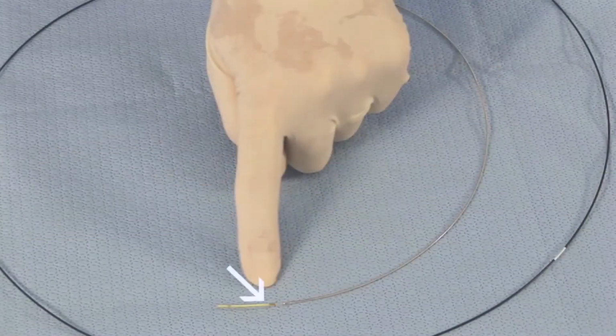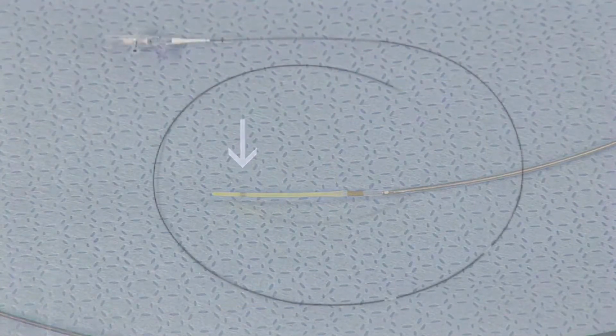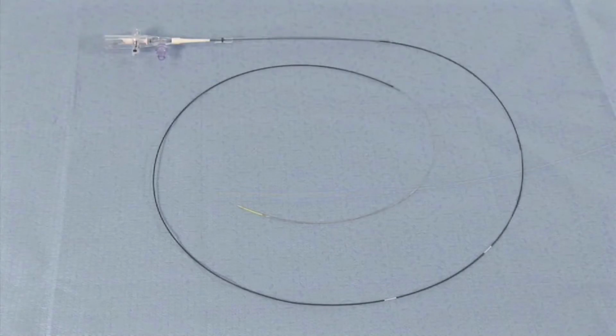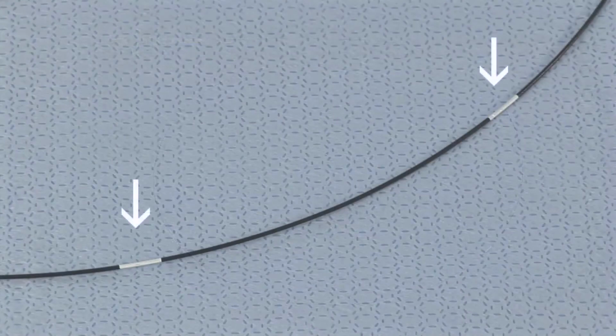The catheter body has a rapid exchange guide wire lumen with an exit port located 15.5 millimeters from the distal end. One radiopaque RO marker band is located 0.5 centimeters from the tip. In addition, guide insertion markers are located on the catheter body at 90 centimeters and 100 centimeters from the distal end.